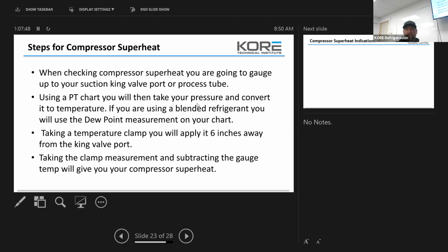Because I can't tell you how many times it's like the third or fourth compressor. I'm like, has anybody checked if it's running good? What are our compression ratios? What's our superheat? And then 9 times out of 10, I go, oh, I'll check that this time. Okay. Let's do that, because now something's taking it out.